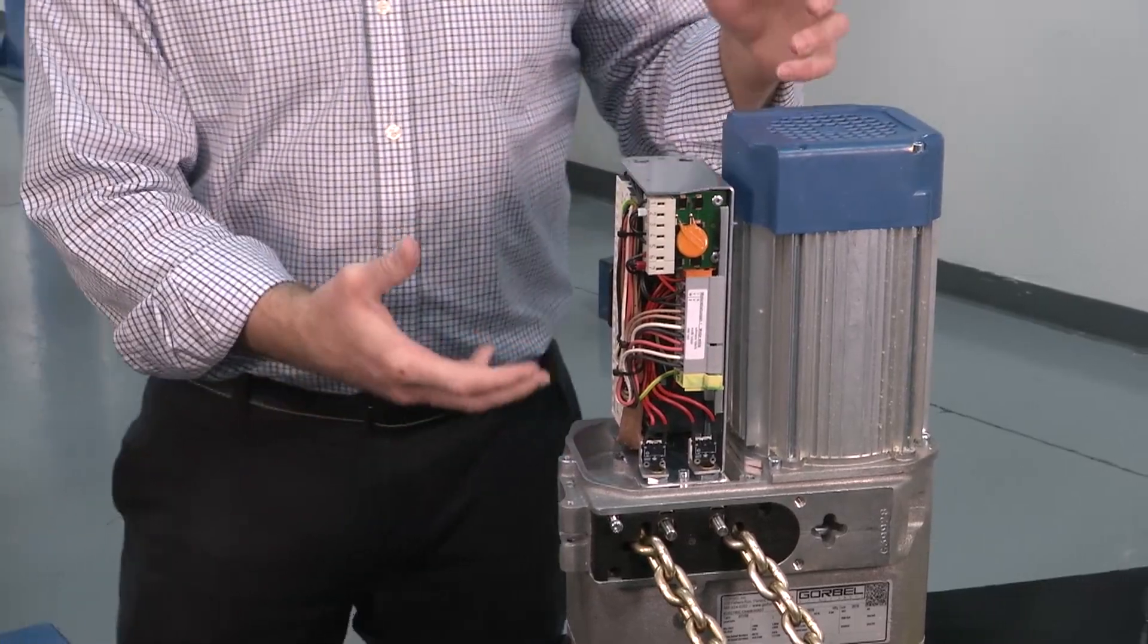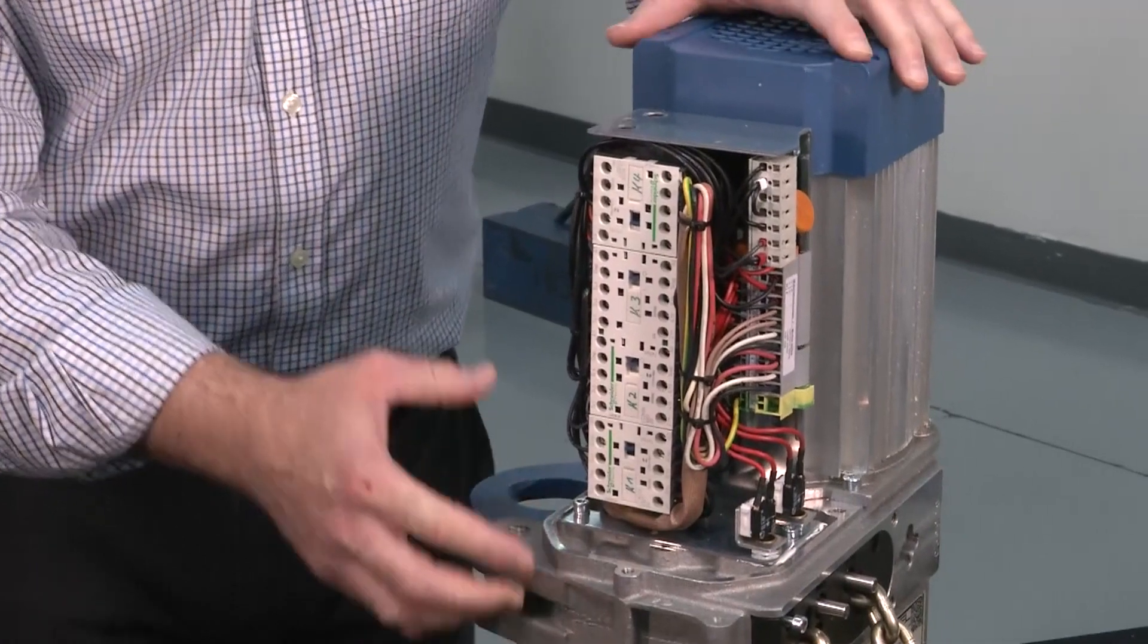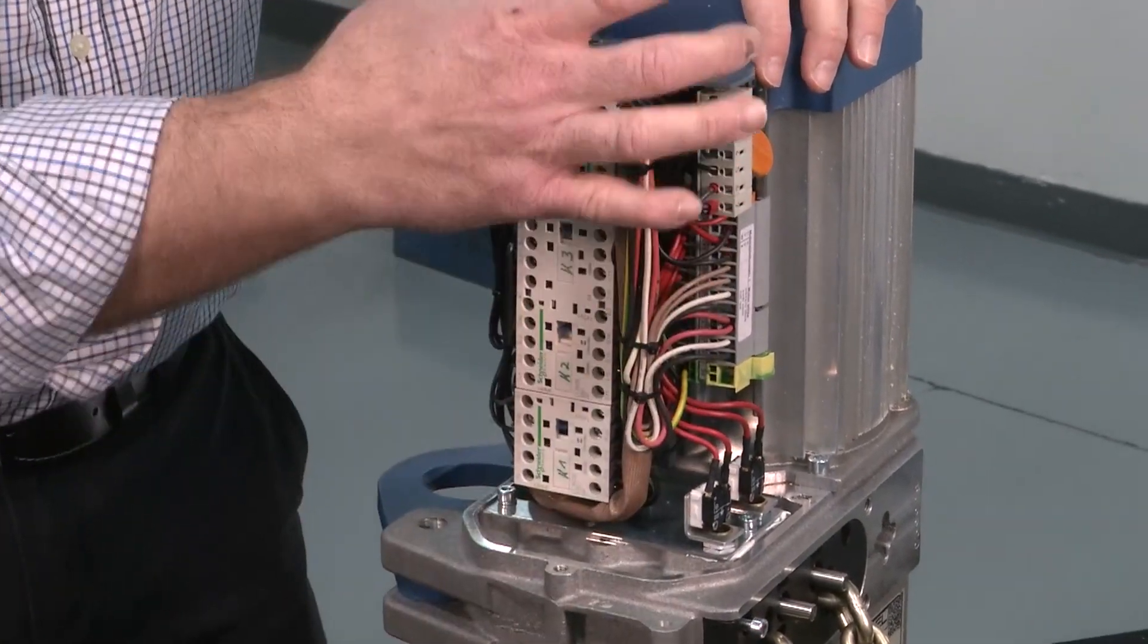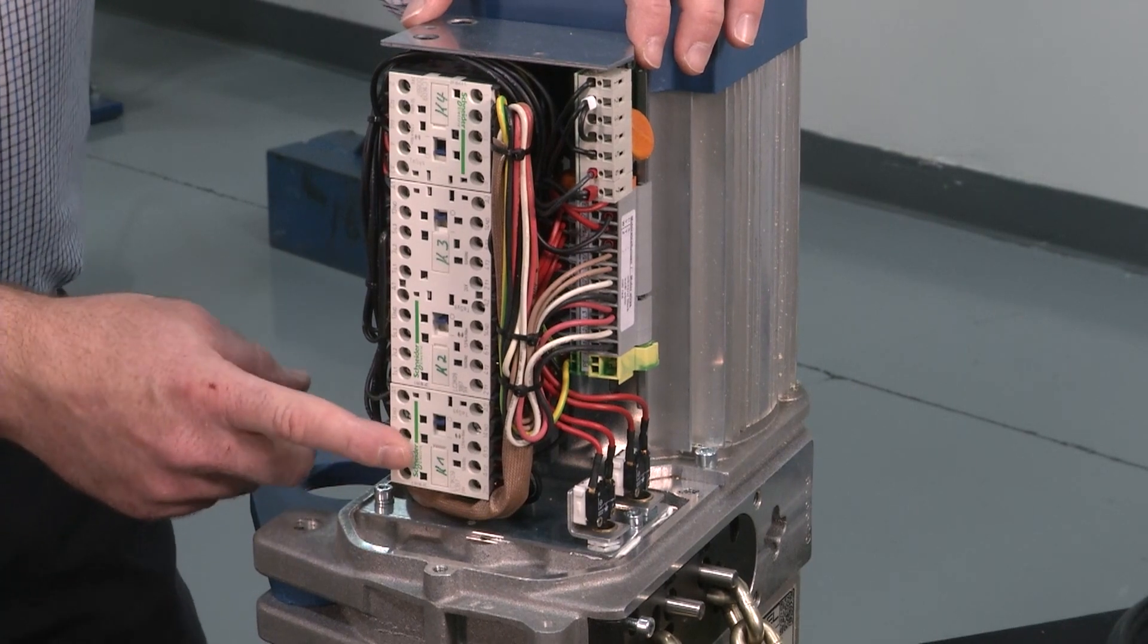So I've taken those off by loosening the bolts before we got ready to go here, and you'll notice here you have in one nice module all your contactors. Now one thing to note is every GS hoist has a mainline contactor, a true mainline contactor.